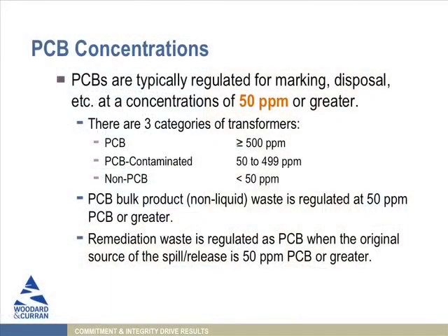Okay? So again, the key point is you want to always be thinking about it when you've got 50 parts per million or greater. And one key point here is that if you have waste, if you've got a spill, a release, if the original source, the original transformer in this case, had a concentration at 50 parts per million or higher, even if the spill ends up being diluted, the original source is 50 parts or more, then you have to consider it as being subject to the PCB regulations.